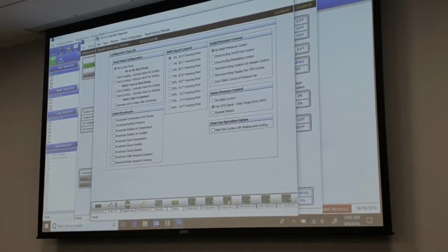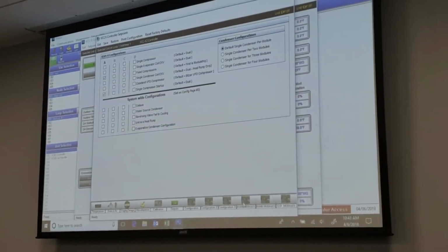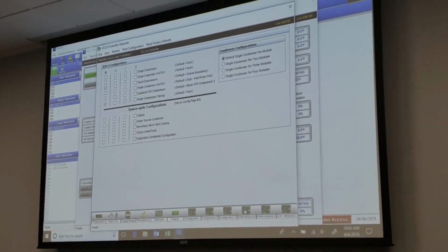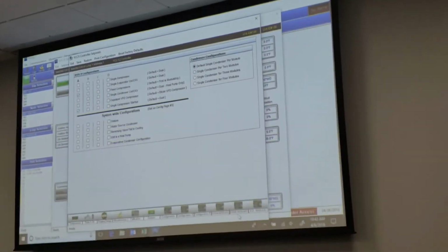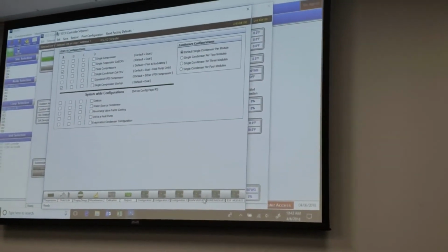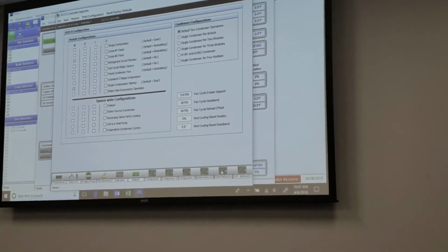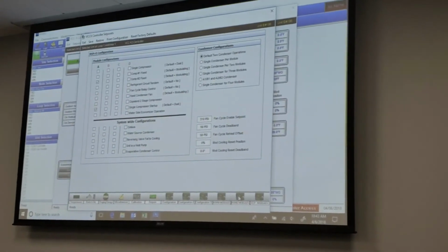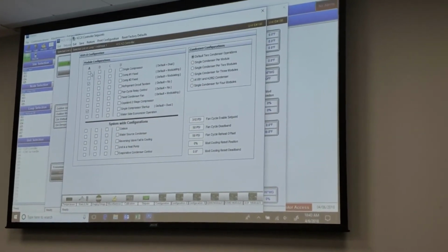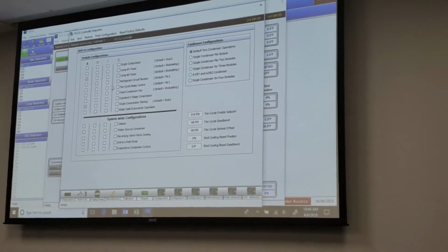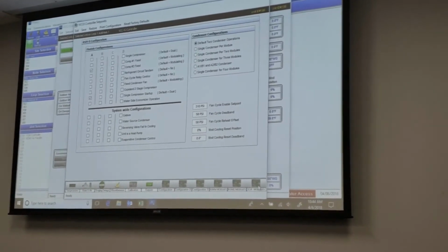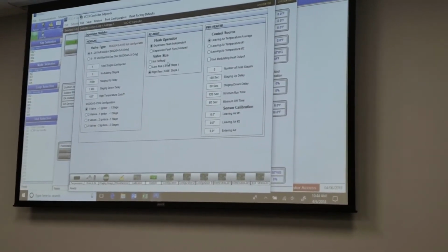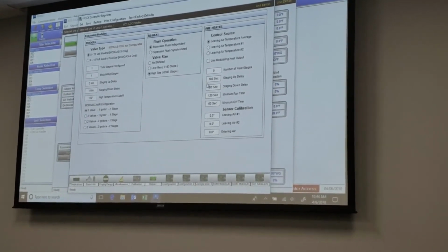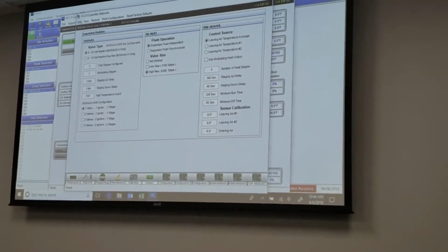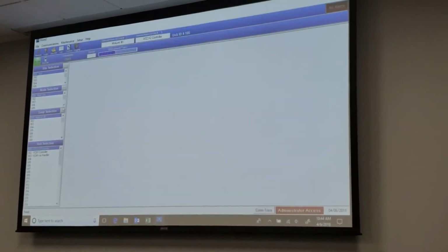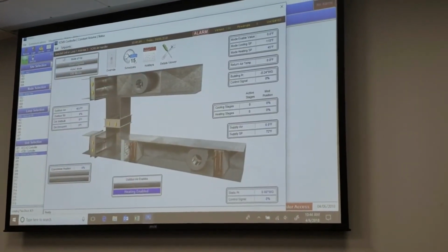So you've got all that. And then when you get into the RSMs, which are refrigeration modules, that's the newer generation stuff. You can do single compressor startup, dual compressor startup. RSMV stands for VFD driven compressors. RSMD is going to be digital compressors, the modulating digital compressors that we talked about. So you've got configuration screens for module A, module B, module C, module D, and then you've got expansion modules: mod gas, reheat, preheat. So you've got a lot you can do with those guys. Now let me jump back to the VCMX. Let me see if there's any trend data on that guy.